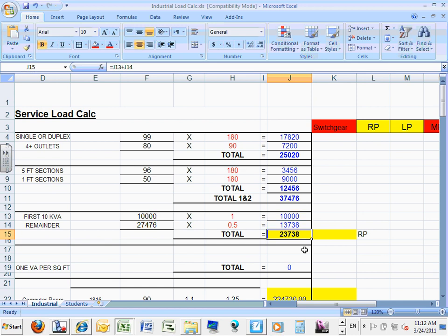Now, Mr. Bew, this is where I want you to wake up. Now I know this number is going to be coming from the receptacle panel. Look what I'm going to do, guys. Right next to the receptacle, equal, and bam, pick it up. And now I not only sized the switch gear, but I also sized the receptacle panel at the same time. And do you guys think that this derated is going to be also under the switch gear? Equal, and pick this one. Bam.